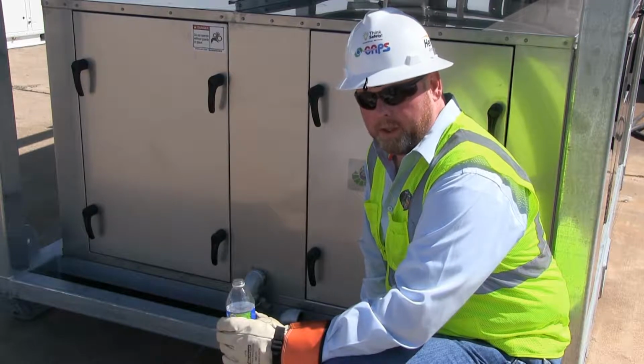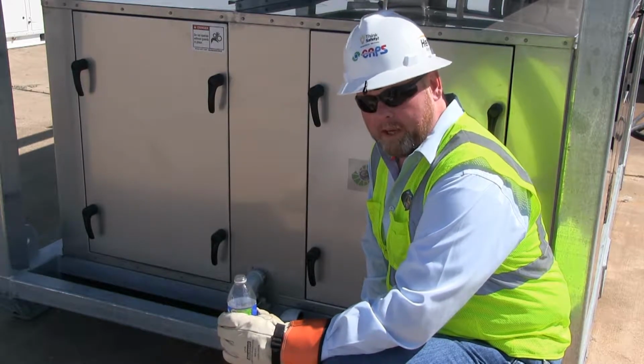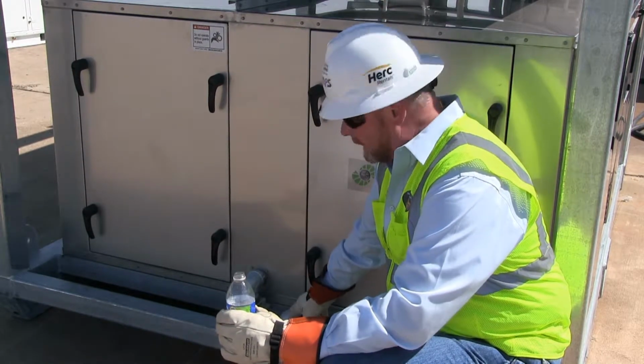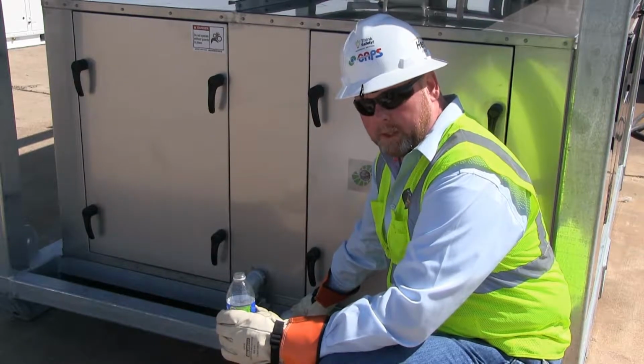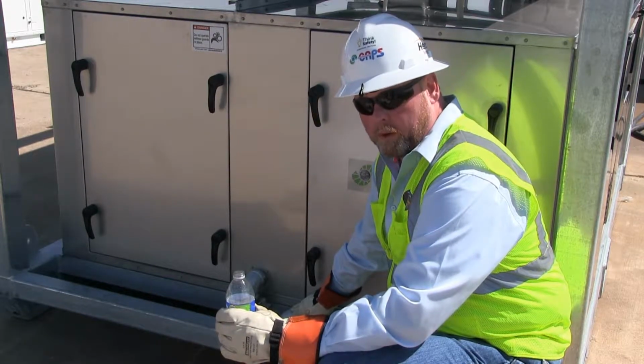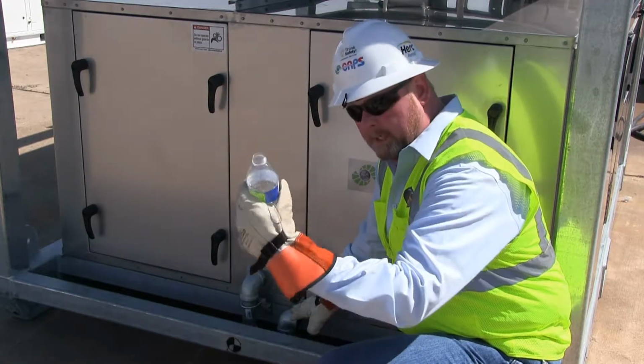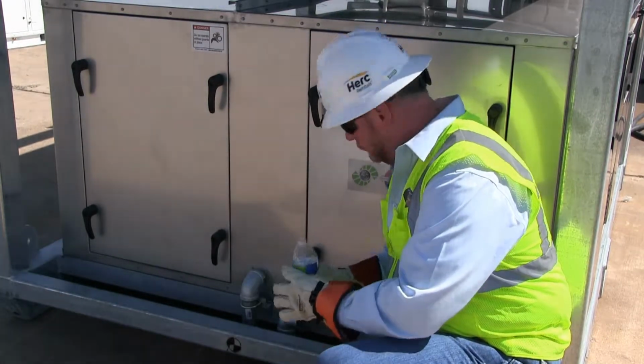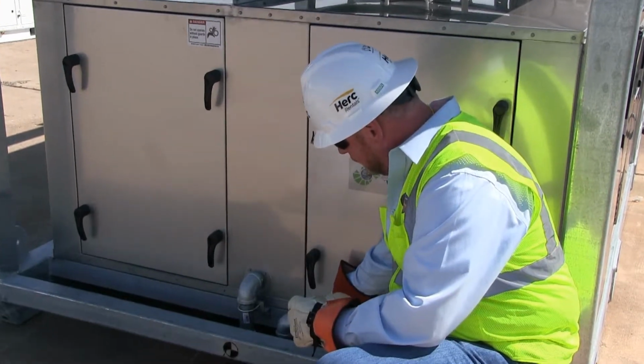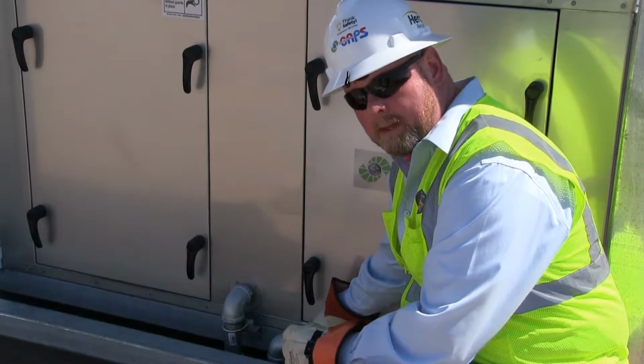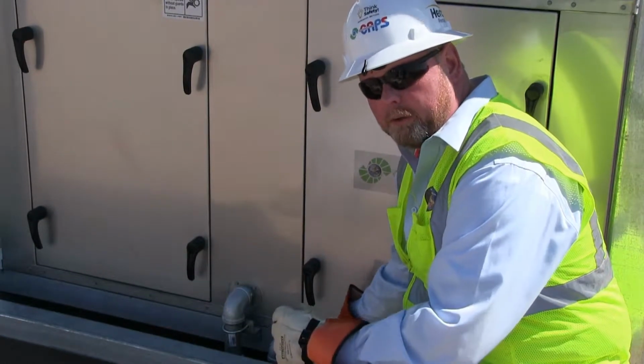Before we put our unit in operation, all of the HVAC units have a condensate P-trap on them. During transport, they'll dry out or the water will be splashed out. So you want to take a bottle of water or a hose, and you simply want to fill the P-trap up. This will prime it to ensure it drains properly during operation.